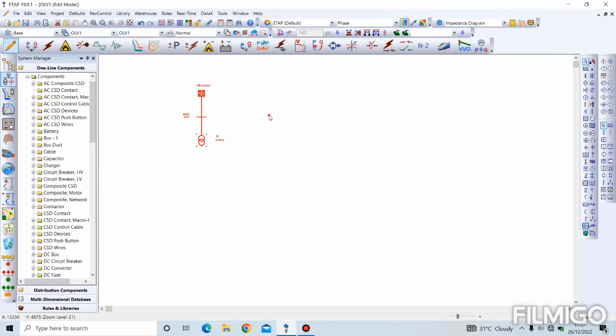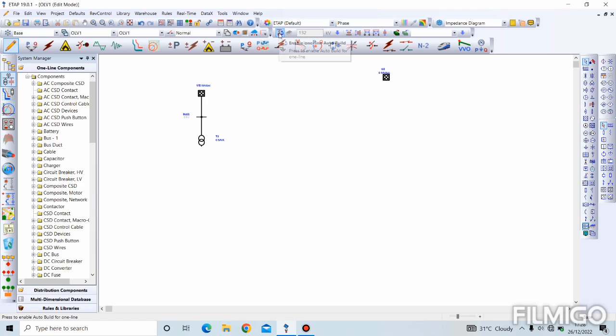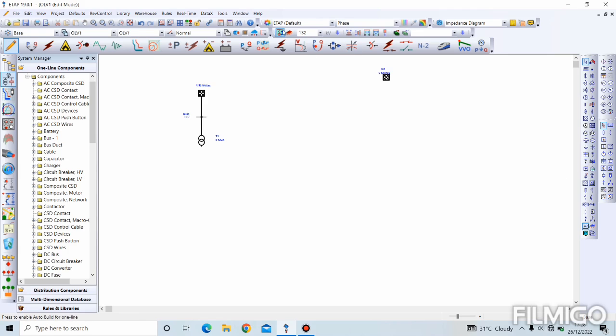I will show you a faster way now. If we take a power grid, we want to model this same single line diagram. We come here. It's called auto build. Enable one line auto build. You click on this. Then, you click on your power grid. Now, if you notice, some of the components are grayed out. Once I click on the power grid, if I remove it, all the components are active. A feature this auto build produces is it allows you to know the components you can connect together.